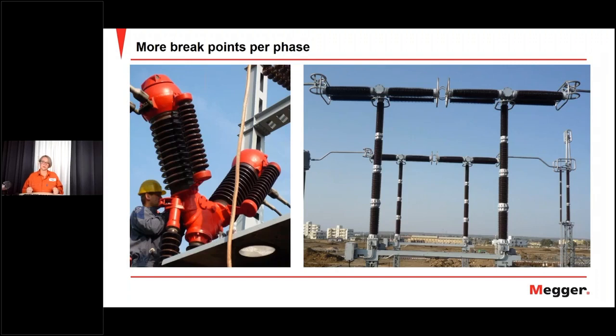What you can see on these pictures also is that you have parallel circuits over the poles here, a grading capacitance, and here you have both grading capacitance and PIR, pre-insertion resistor contacts, which are often used on higher voltages. It's a cheaper solution than to use synchronized switching, which is a more modern way to solve the problem that you need the voltage distributed over the whole four breakpoints on the phase. Sorry, the grading capacitance is that. The PIR is to limit the current during the closing. Said the wrong word here.